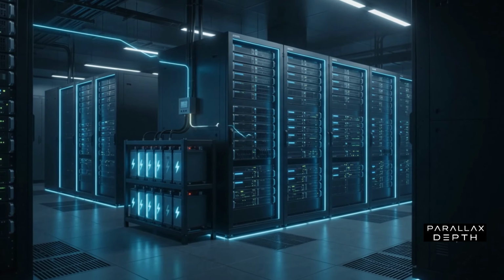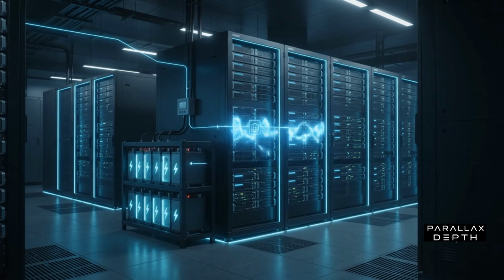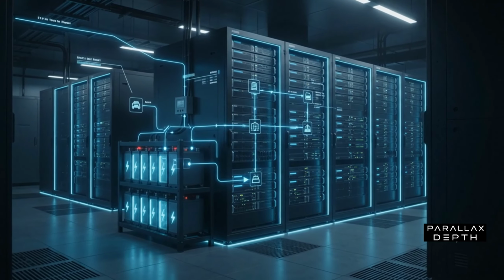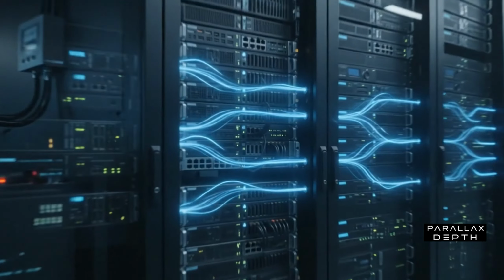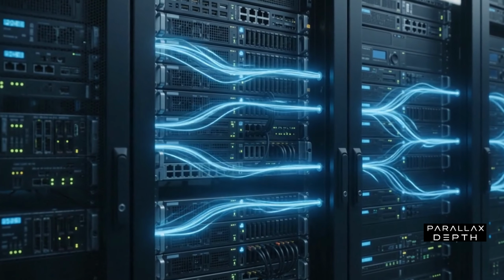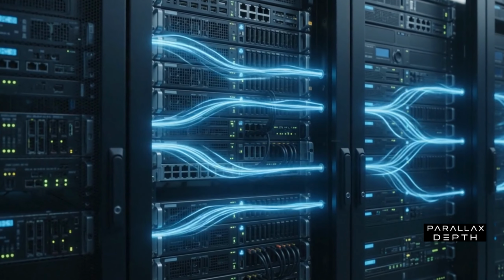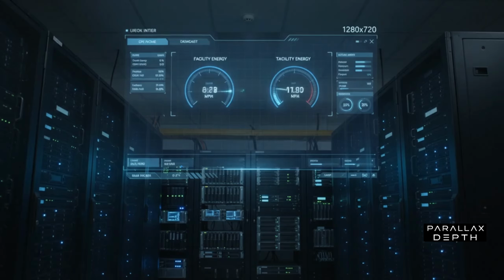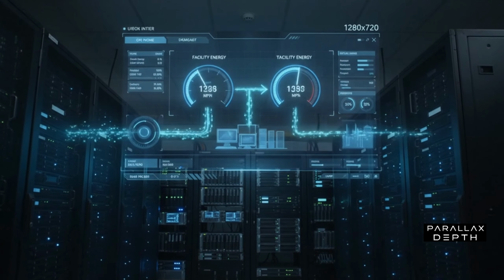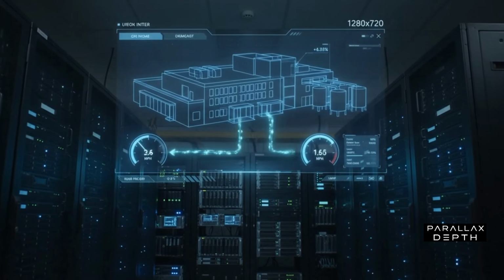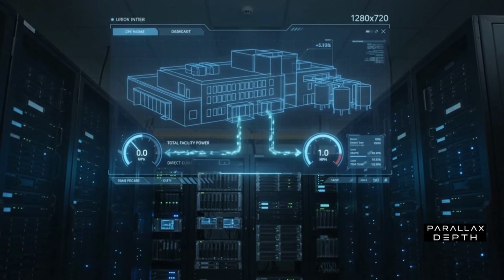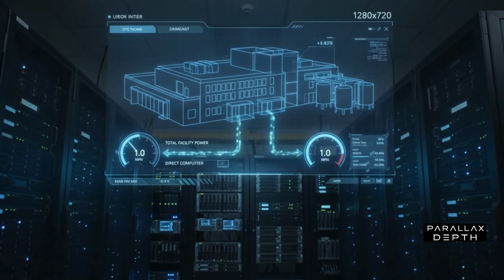Engineers measure this overhead with a number called Power Usage Effectiveness, or PUE. It compares the total energy used by the facility with the energy delivered directly to computing equipment. A perfectly efficient building would have a PUE of 1, meaning every unit of electricity goes to the computers. Real facilities are always above 1 because cooling, power conversion, lighting, and other systems also consume energy.